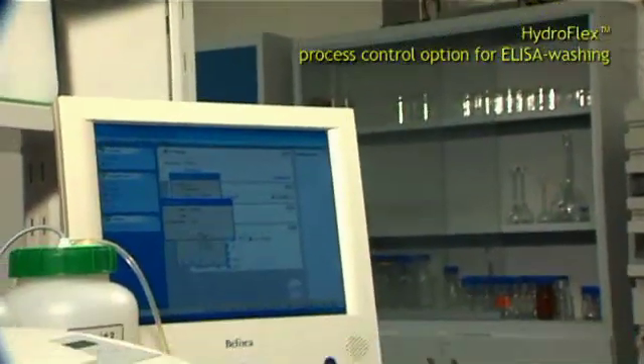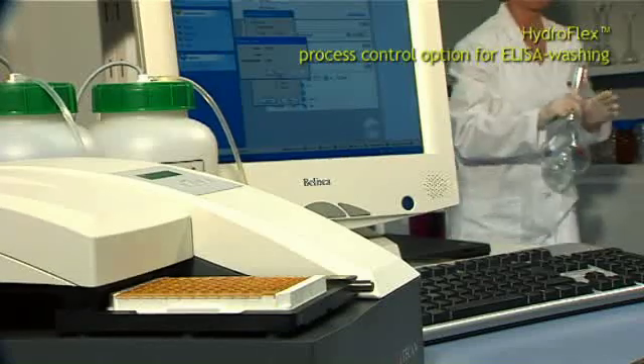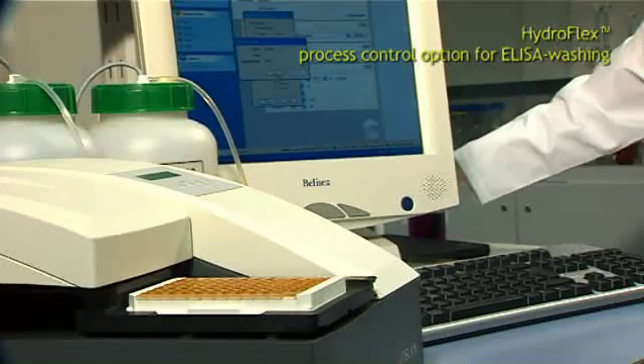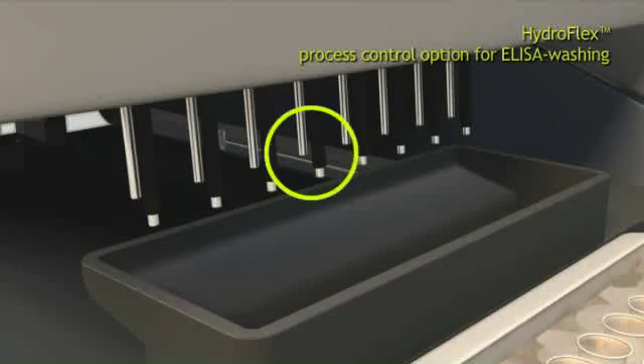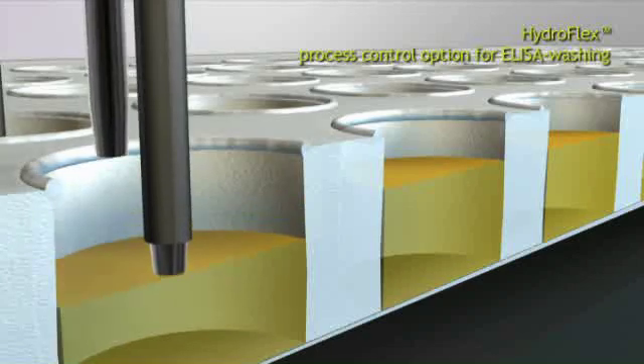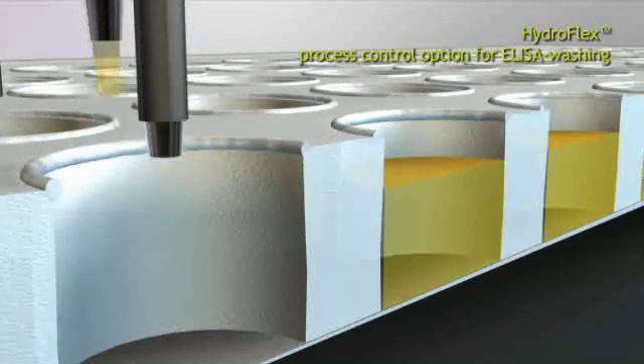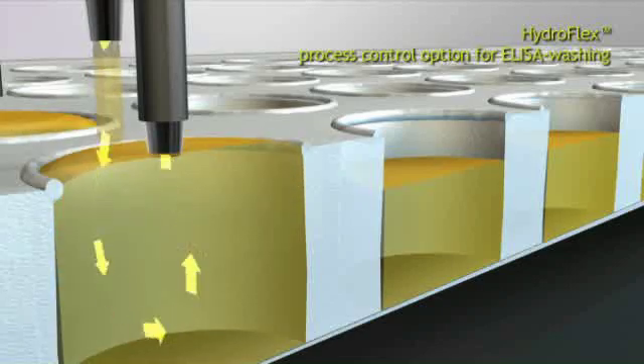Tecan improved the HydroFlex's performance in ELISA washing by developing an option called process control. The monitoring of the wash step is done via an advanced wash head with extended detection function. The process control monitors whether there is an electrical circuit made between the respective dispense and aspiration needles.